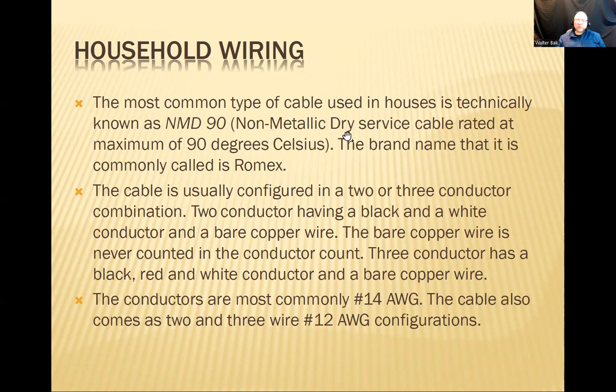You're not supposed to have that thing regularly exposed to moisture. So in the walls, you're not supposed to have moisture. If you do, you have a bigger problem than that, as I said before. It's a service cable rated at the maximum of 90 degrees Celsius. It's supposed to withstand 90 degrees Celsius. Water boils at 100 degrees Celsius, so it's pretty close to boiling water. So that's pretty hot. You won't be able to withstand that. You can't touch 90 degrees with your bare hand. You're going to get burnt.